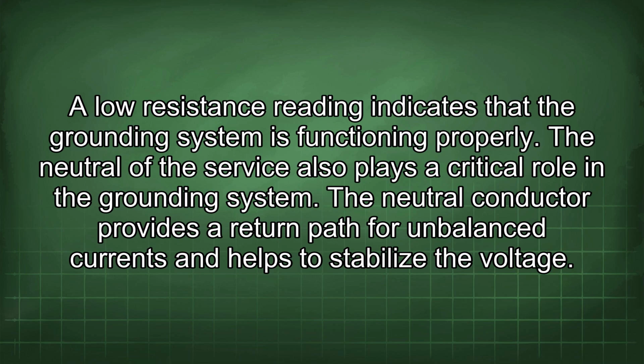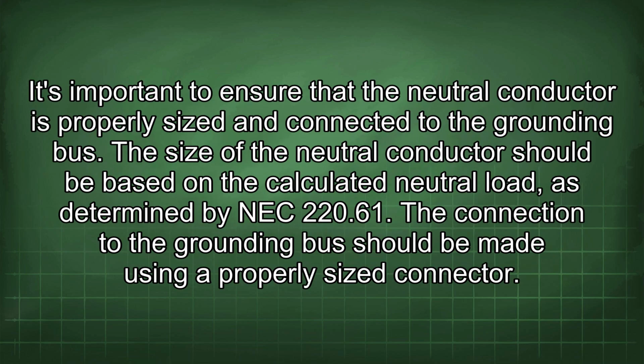The neutral of the service also plays a critical role in the grounding system. The neutral conductor provides a return path for unbalanced currents and helps to stabilize the voltage. It's important to ensure that the neutral conductor is properly sized and connected to the grounding bus. The size of the neutral conductor should be based on the calculated neutral load, as determined by NEC 220.61. The connection to the grounding bus should be made using a properly sized connector.